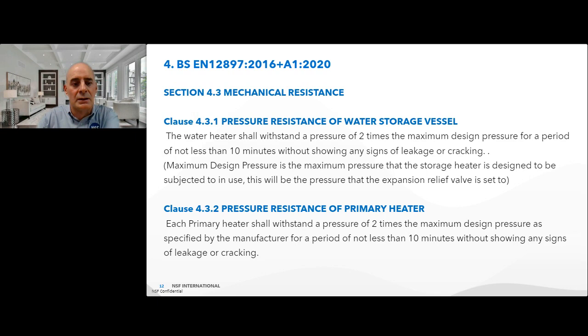Clause 4.3.2, pressure resistance of primary heater or coil. Each primary heater or each coil should withstand a pressure of 2 times the maximum design pressure as specified by the manufacturer for a period of not less than 10 minutes without showing any signs of leakage or cracking. So if there's multiple coils within the cylinder and there's different pressure ratings, then these pressure ratings will need to be stipulated on the label as well. And as I said, each coil then will be tested to twice that working pressure.